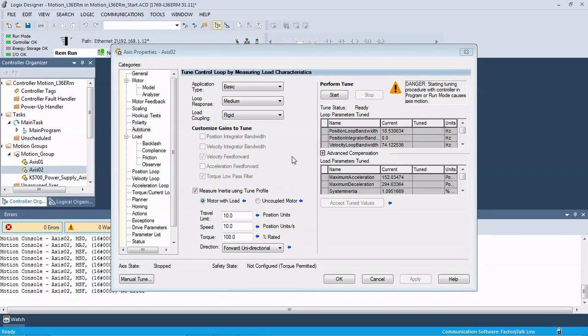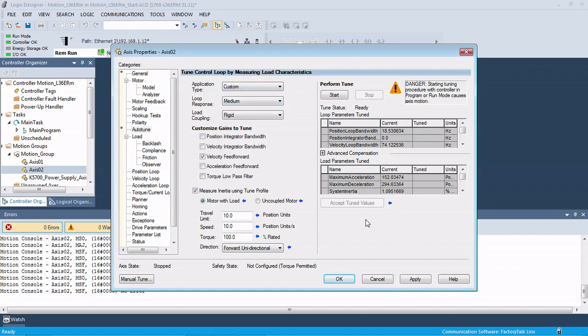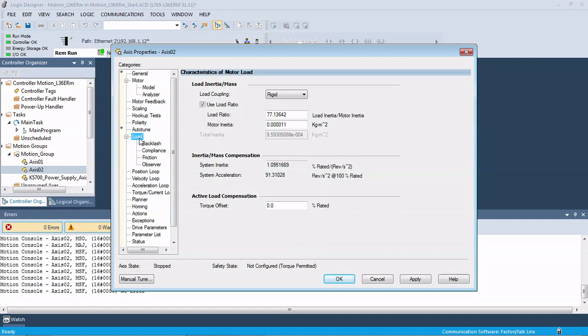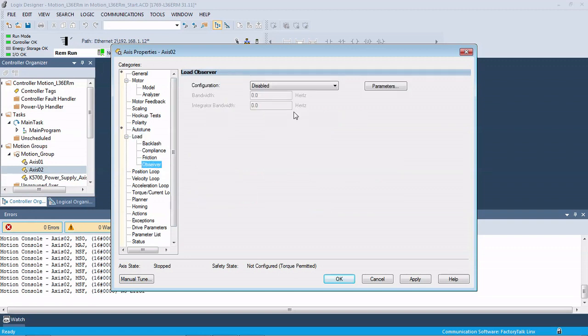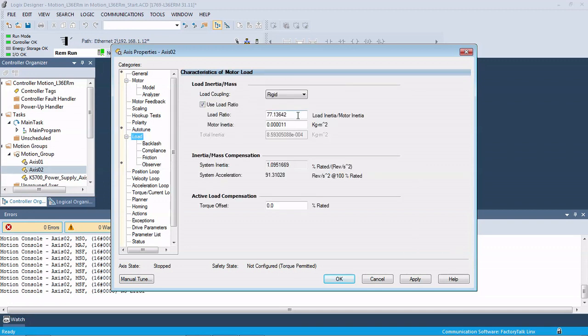The first thing we're going to do is come to the auto-tune and change this to custom and uncheck the torque low-pass filter. From there, we're going to go to our load over here on the left-hand side. Under Load Observer, we're going to enable Load Observer with Velocity Estimate and make sure this is set to zero initially. Also under the load, make sure that the load ratio is set to zero.